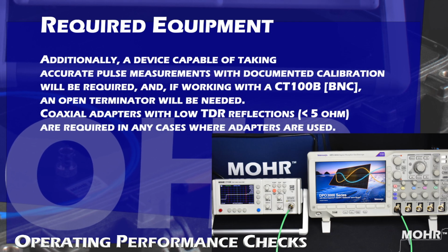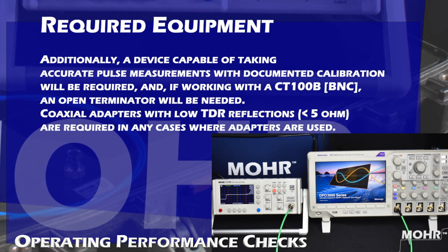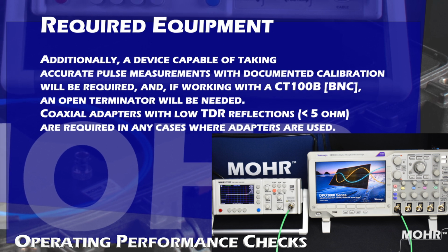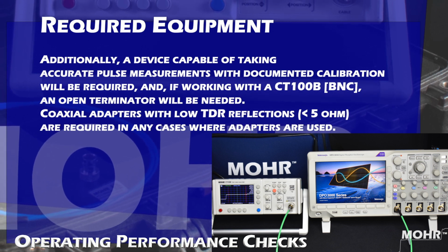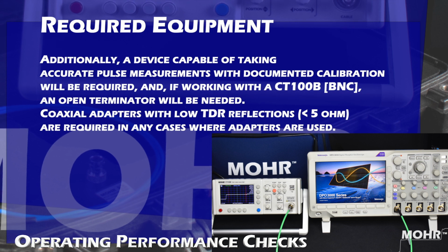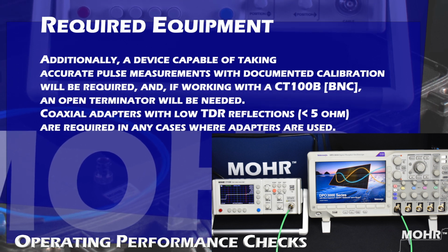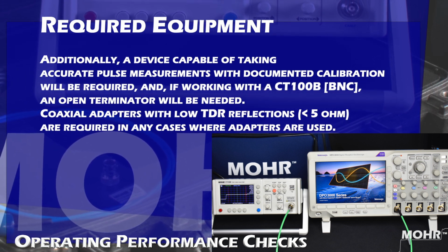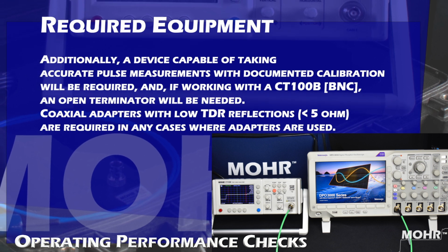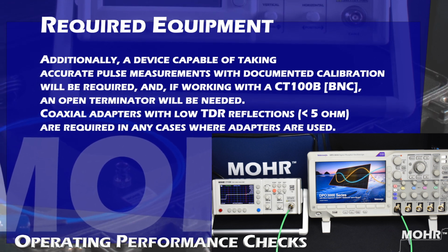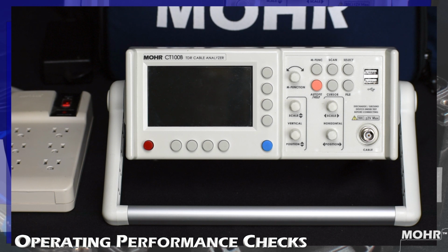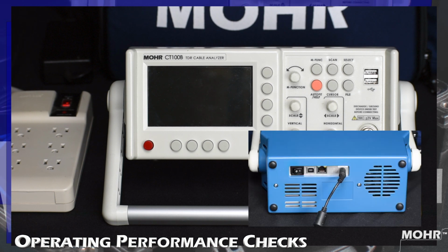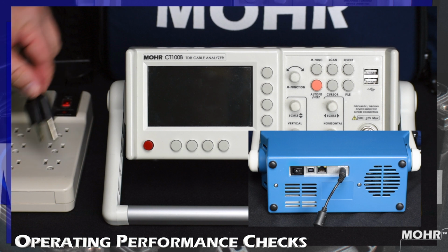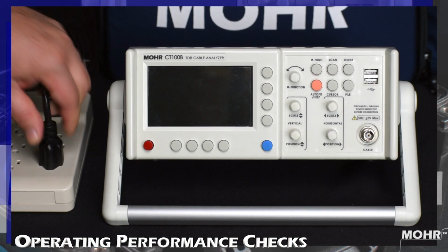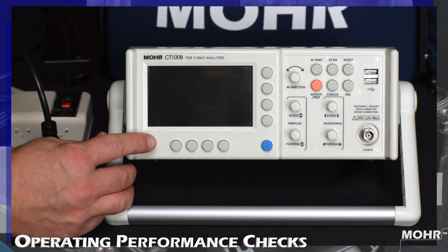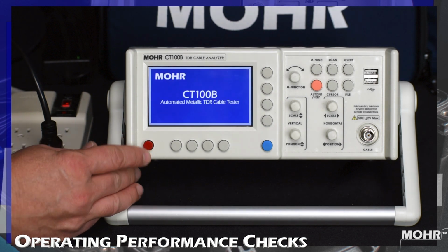Additionally, a device capable of taking accurate pulse measurements with documented calibration will be required, and if working with a CT100B BNC, an open terminator will be needed. Coaxial adapters with low TDR reflections of less than 5 ohms are required in cases where adapters are used. Getting ready for our test, we're going to disconnect any cables from the front BNC or SMA connector and connect the instrument to the external 24-volt power supply and connect to a standard 3-prong AC source.